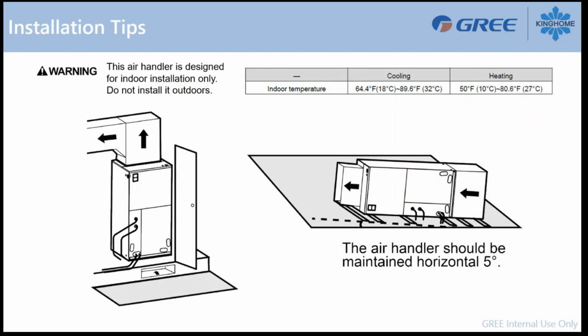Those air handlers can be installed vertically or horizontally. So upflow like this one, or on the left side or on the right side. This air handler is designed to work only in indoor operation or indoor temperature. If you are out of range, maybe you will have a lack of performance in the unit. You always have to install those units inside a room that is heated.